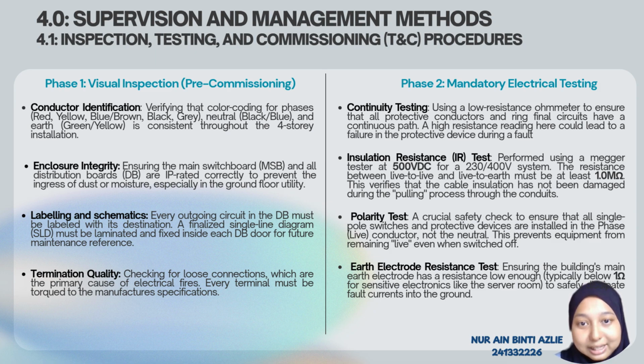Lastly is termination quality, checking for loose connections, which are a primary cause of electrical fires. Every terminal must be torqued to the manufacturer specification. Second phase is mandatory electrical testing. These tests are performed using calibrated instruments to verify the electrical integrity of the wiring. First, we need continuity testing, which uses a low resistance ohmmeter to ensure that all protective conductors and ring final circuits have a continuous path. A high resistance reading here could lead to a failure in the protective device during a fault.